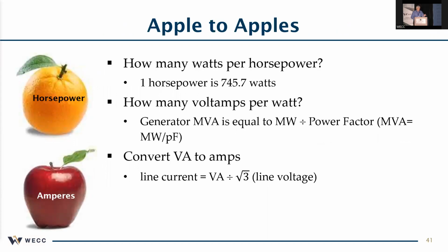So this applies to that conversion piece, but it also applies to anything else you do in facilities. You need to be able to compare apples to apples. Most current carrying equipment is rated with a current value. Things like transformers sometimes give an MVA value, and generators give MVA. You can convert those MVAs into current, but in order to find what's limiting, they need to be in the same units. Auditors tend to prefer current instead of listing everything in volt-amps. So think about that. You have a transformer with an MVA. When you're looking at the pieces on the high side, convert that MVA into a current. When you're looking at the pieces on the low side, convert the MVA into a current on that side to come up with the most limiting component.